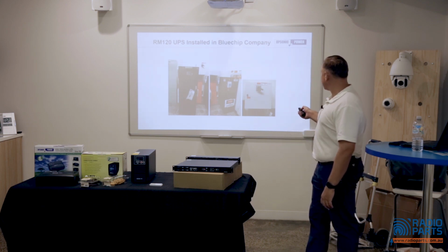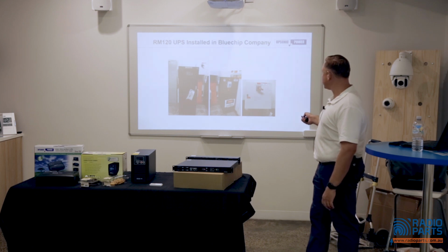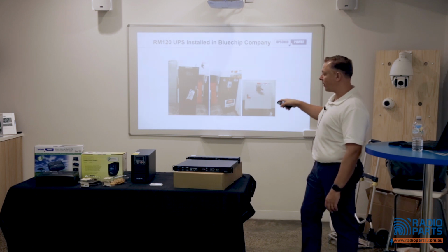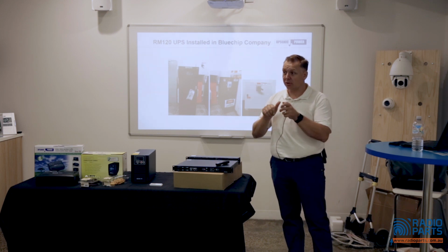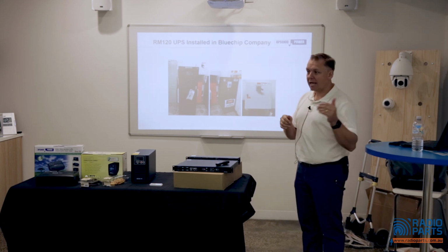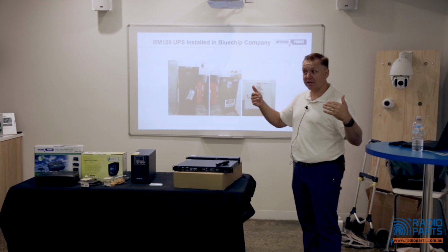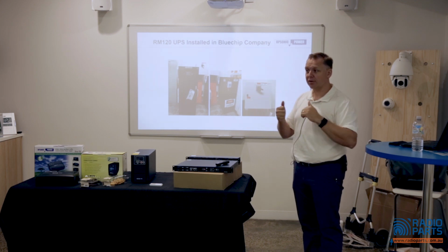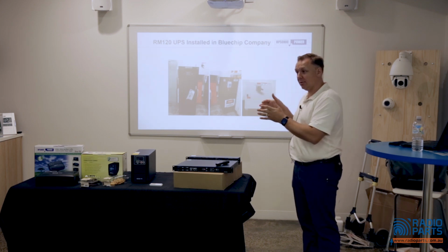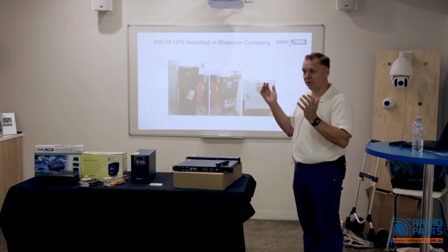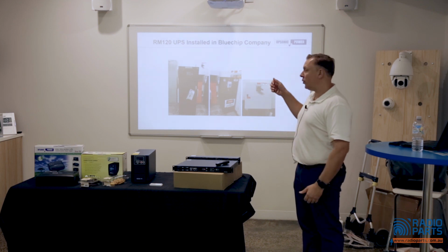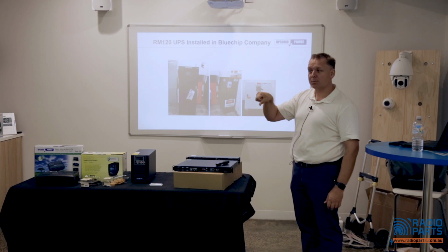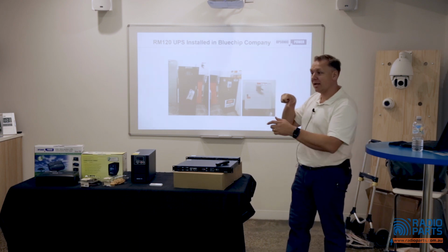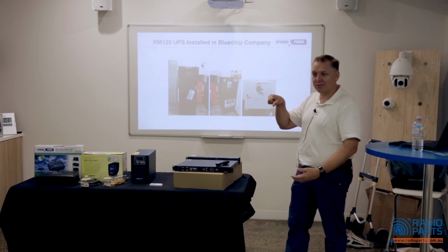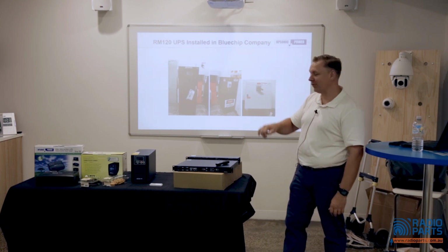An important consideration that you can't see in that photo is that all of these, when you get to 3-phase, have an interlock button as well, because the input and output of a UPS can be out of phase with each other. And if you just operate the switch without the UPS being in static bypass, you can blow the whole thing up. So before you can rotate the switch, you must press a button, and the button tells the UPS to match the input and output up together, so everything's happy before you can rotate the switch.